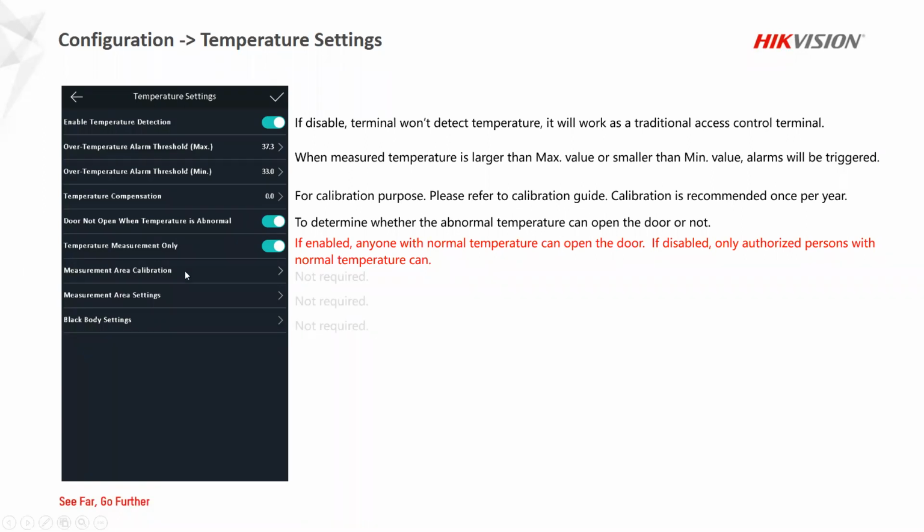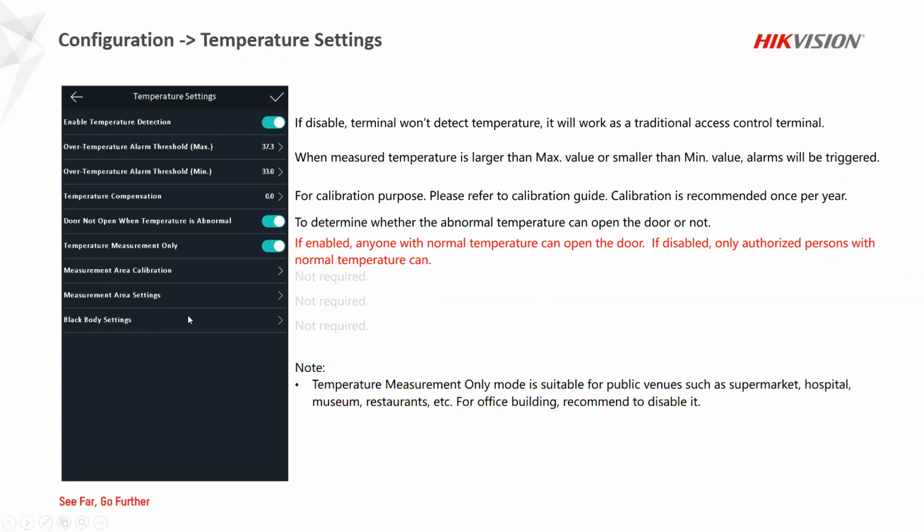So the other three settings are not required for the first time, but if you are going to use a black body to increase the accuracy of the temperature measurement, then we have another guide for that purpose. It's also quite easy, not that difficult.